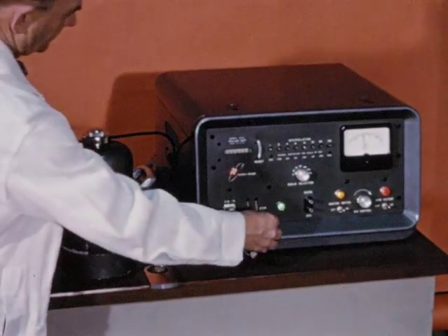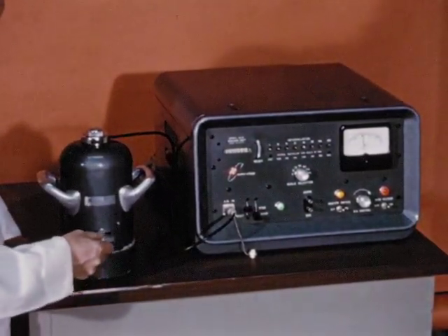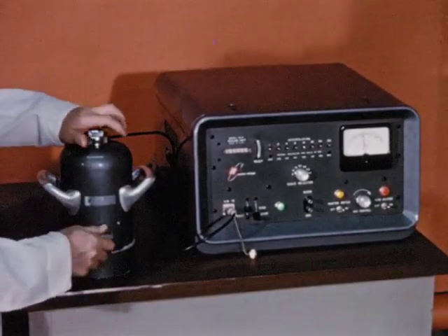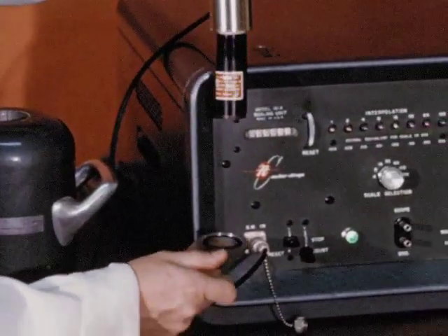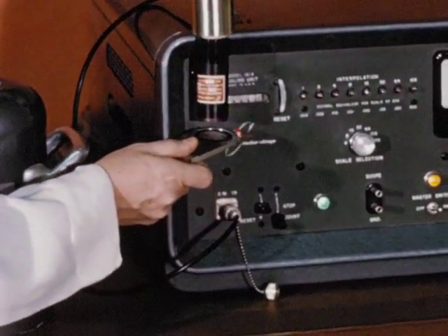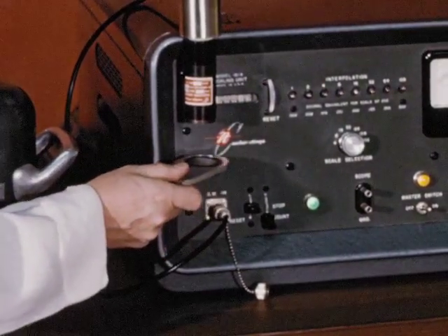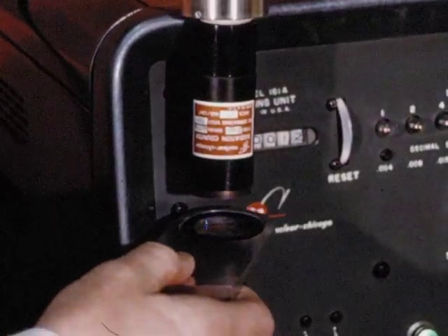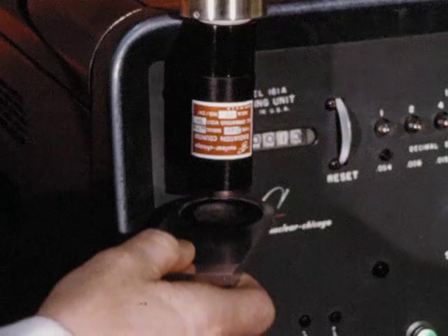Geiger counters and other types of radiation counting instruments also depend on ionization for their operation. Radiation ionizes molecules of a gas within the Geiger-Müller tube. Each time molecules of the gas ionize, energy is conducted in small bursts between 2 electrodes in the tube at high voltage. These bursts of energy are mechanically counted, giving us a measure of the radiation being emitted.